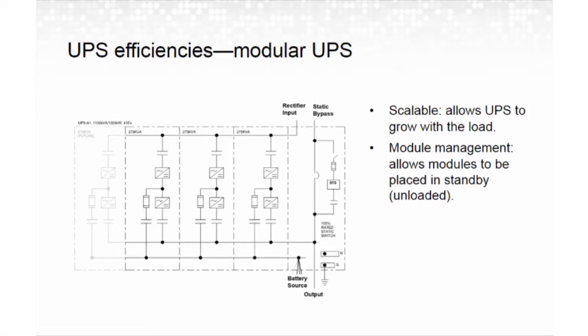One of the ways to do that is with a modular UPS. A lot of the manufacturers are now providing UPSs that are actually smaller components put into one component. So there might be, in this graph, 275 kW UPSs that make up an 1,100 kW UPS total. What that allows you to do is grow with the load. So you can put in two modules or three modules, and then as your load grows, you can grow with it. And what that does is those two modules now operate higher on the efficiency curve than if you had all four operating at one time.